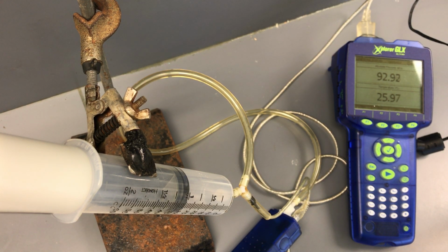We've kind of gone up and down. If you take a range of those values, it really doesn't matter exactly what number you get. We're going to try to get something as close as we can that's consistent. We'll let it become steady and calibrate itself. If we look at our first number, now we have a pressure of 92.91 or 93. Again, you don't have to be exact here, just pick a number in that range. Notice how it was 92.89, then 92.94, 92.92. Find a number that's happy in there.